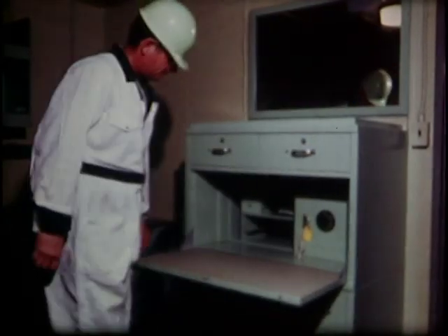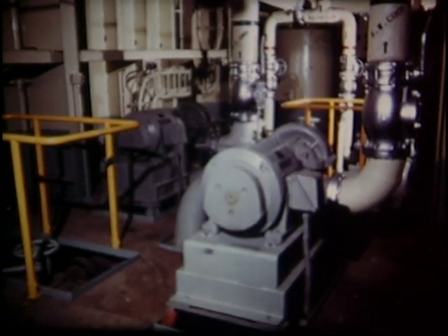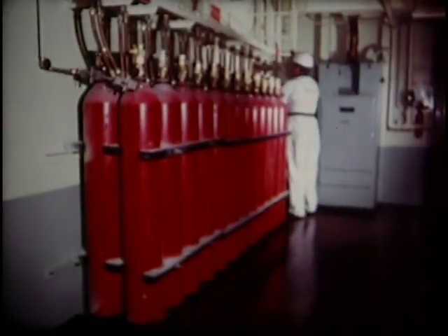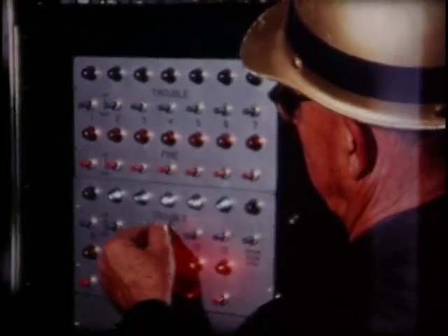Tests of the provisions for life aboard ship were not overlooked. Both the primary plant and the secondary plant contained numerous heat exchangers; typical is the purification cooler. In addition to the usual 4-hour pump runs, flow rates were set for the cooling water systems serving these heat exchangers. Tests of other secondary plant and ship service systems included those of the bilge and ballast system, the potable water system, and the make-up feed system. Fire protection equipment was thoroughly checked and demonstrated: the freshwater and saltwater firefighting systems, the CO2 firefighting system, the smoke detecting system, and the fire alarm system.